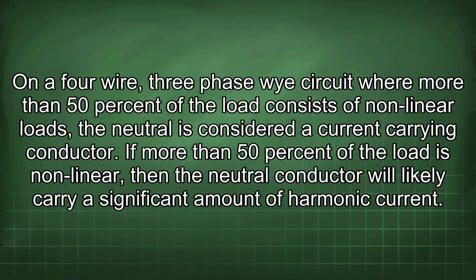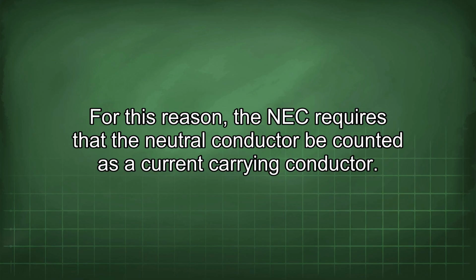On a 4-wire, 3-phase Y circuit where more than 50% of the load consists of nonlinear loads, the neutral is considered a current-carrying conductor. If more than 50% of the load is nonlinear, then the neutral conductor will likely carry a significant amount of harmonic current. For this reason, the NEC requires that the neutral conductor be counted as a current-carrying conductor.